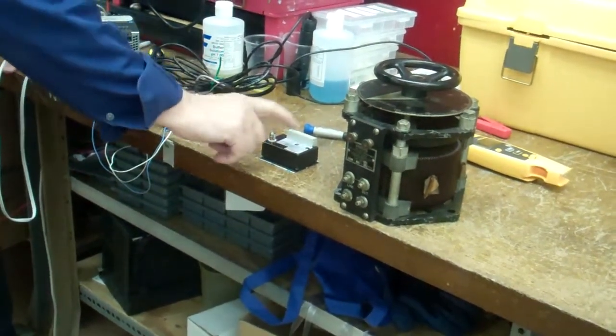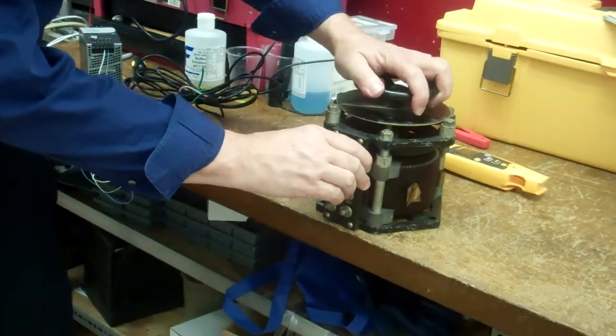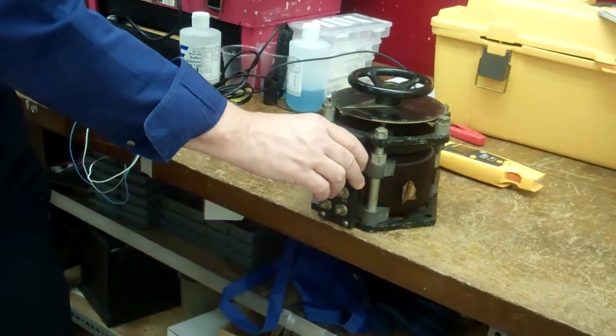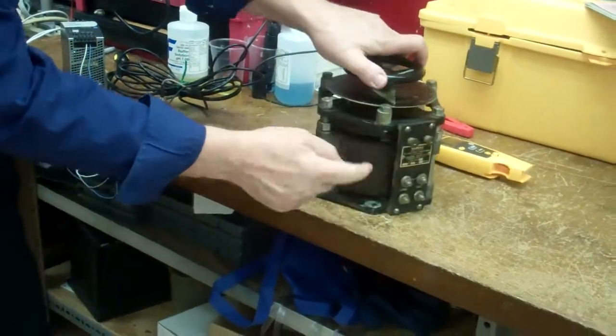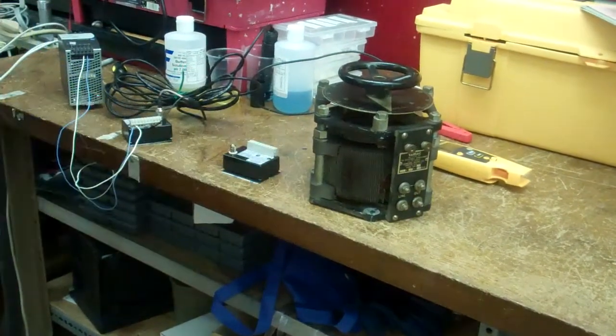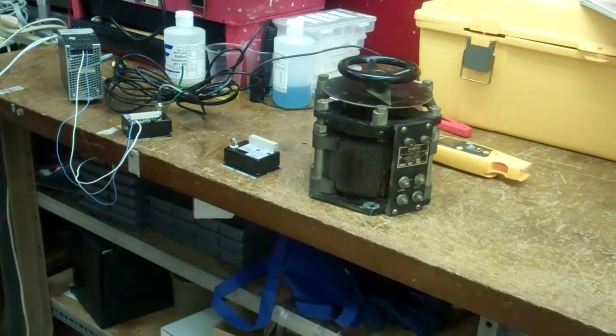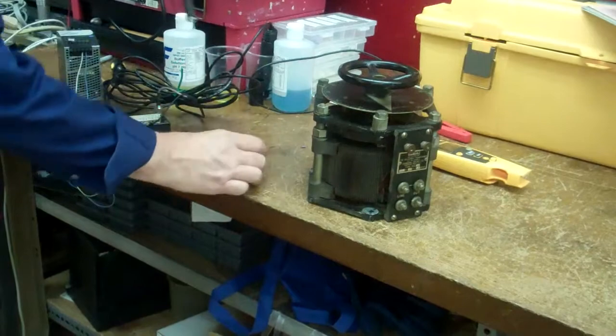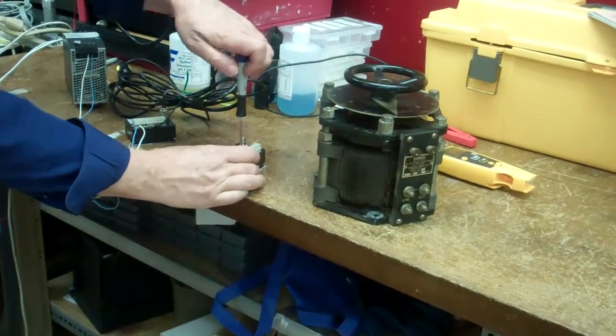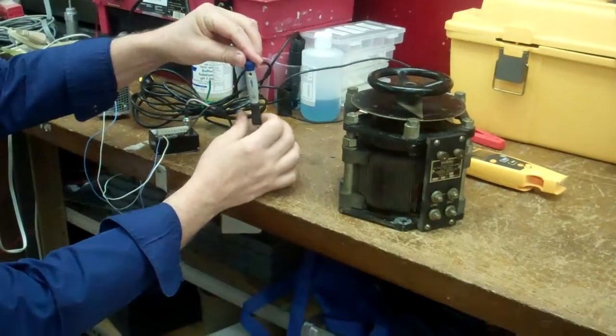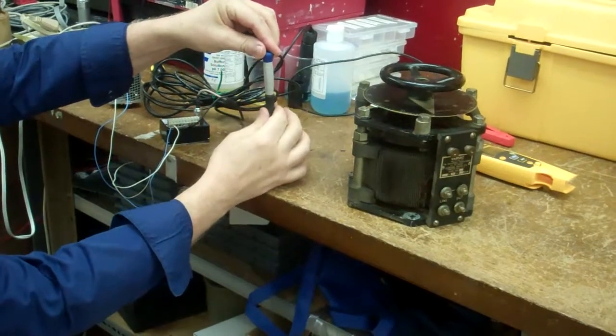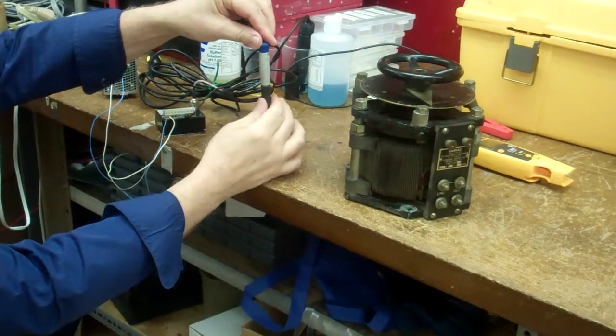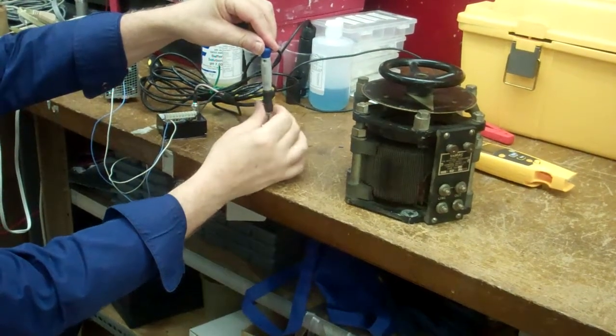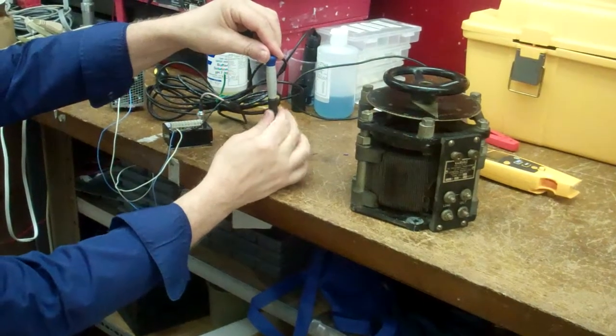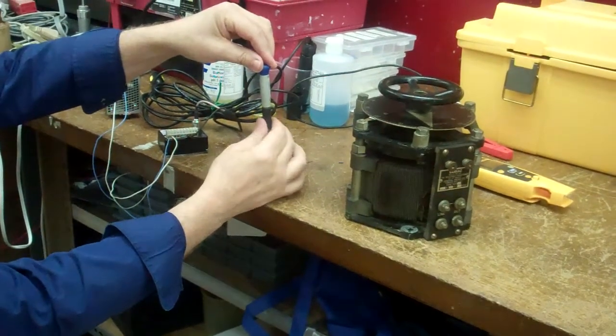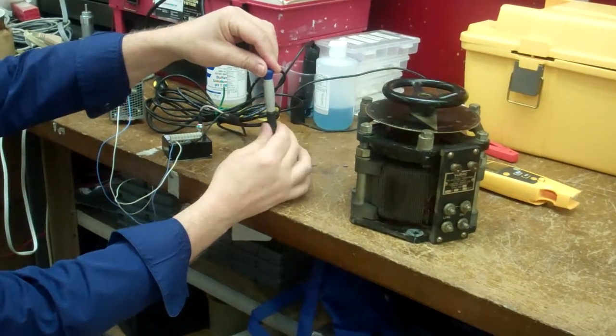The reason they become non-calibratable is the rheostat gets turned past its 0 point and it keeps going. The wiper comes off the metal. So if you have a potentiometer, pH meter, and it won't calibrate, you take a screwdriver, you put it in the first screw, and you turn it counterclockwise 25 times. 1, 2, 3, 4, 5, 6, 7, 8, 9, 10, 11, 12, 13, 14, 15, 16, 17, 18, 19, 20, 21, 22, 23, 24, 25.